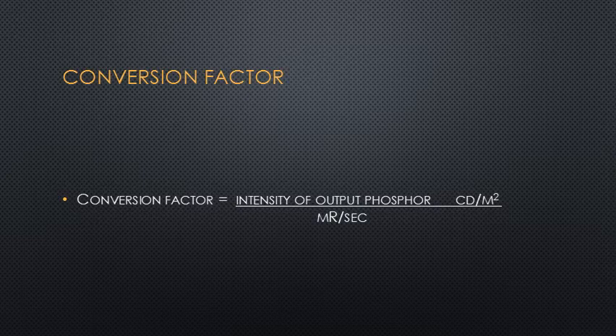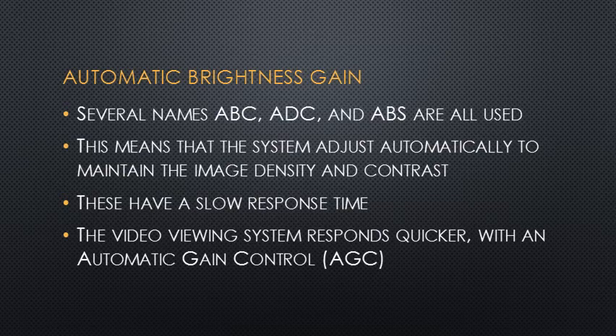Brightness from phosphors can lose luminescence due to age, which occurs about 10% per year. When a phosphor ages, more technical factors are needed. There are different automatic systems used in the image intensification process: automatic brightness control (ABC) is the most common terminology; ADC is automatic dose control; and ABS is automatic brightness stabilization. These systems adjust technique to subject density and contrast automatically by increasing or decreasing technical factors.